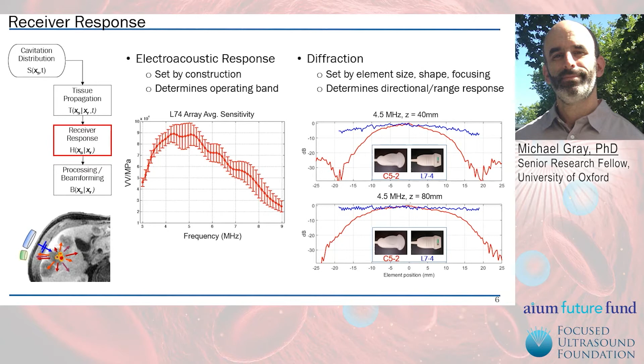But of course, a much bigger effect is seen with the C5.2, owing to the higher angles of incidence on the array's rotated elements. In fact, the response goes through a null and then recovers into a side lobe, which means that the responses would be inverted. And again, if you don't tell the beamformer this is happening, you'll get some pretty strange responses, not the least of which is you've got a big opportunity here for biasing between measurements of the same exact system, but made with two different arrays. Because this is a near-field effect, if we change depth, we're going to see some changes in these patterns as well. And typically, the further away you get, the smoother these patterns get. But the fact that they're changing for both arrays over these distances, again, is an opportunity for biasing as a function of depth. And this might show up, for example, in the difference between monitoring proximal and distal boundaries of a target in a patient.